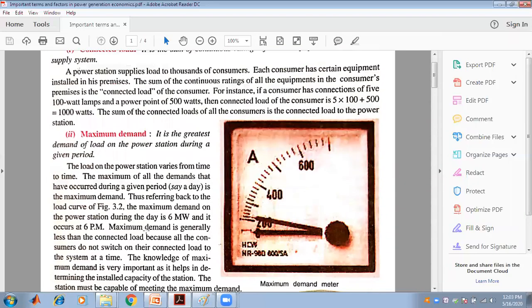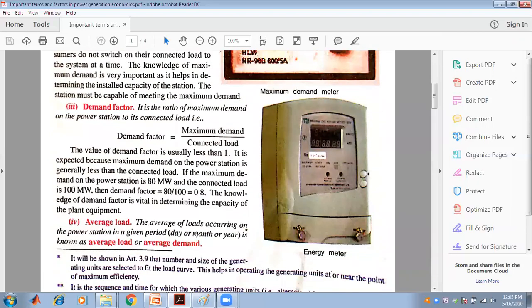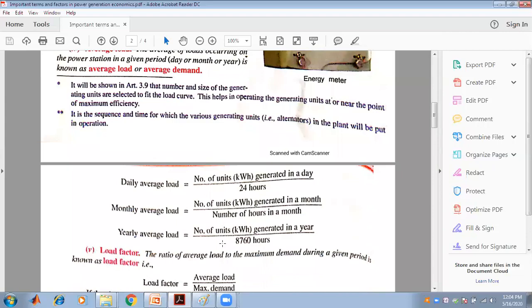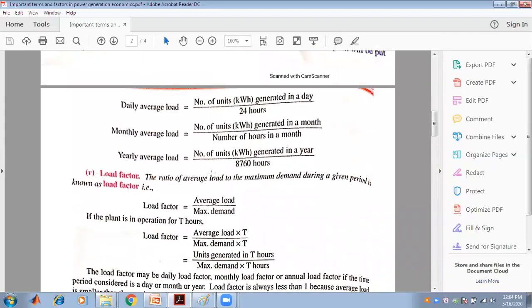The next factor is the average load. The average of all loads occurring on the power station in a given period — day, month, or year — is known as the average load or average demand. The daily average load is the number of units (kWh) generated in a day divided by 24 hours, giving a result in kW.